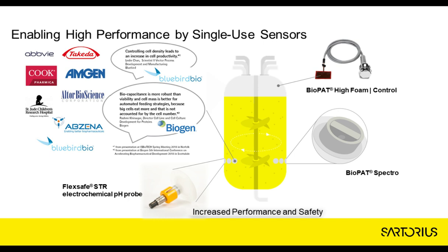The Sartorius FlexSafe pH electrochemical probe is another single-use innovation we have in the market, with a wide measurement range from pH 3 to pH 10 and only 1-point calibration, combining the benefits of multi-use traditional autoclavable probes with the convenience and reduced setup time and effort of the single-use approach.